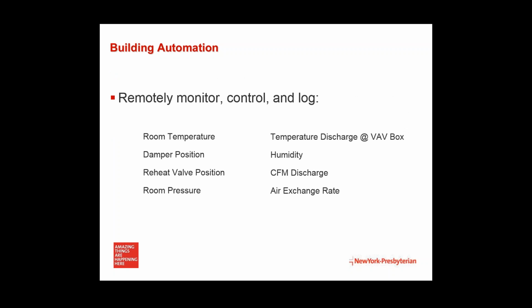As you can see, these are some of the points that we monitor to help us make sure that we're maintaining a safe environment while taking advantage of energy-saving opportunities. Utilizing all these inputs, we have ranges, alarms, and inputs so that all critical care components are taken care of. And whenever a critical point is in alarm, it notifies the engineer to respond accordingly so that we make sure we're maintaining a compliant, safe environment. Next slide.